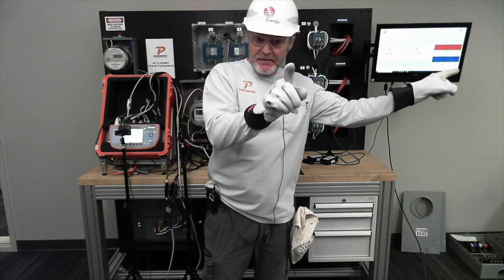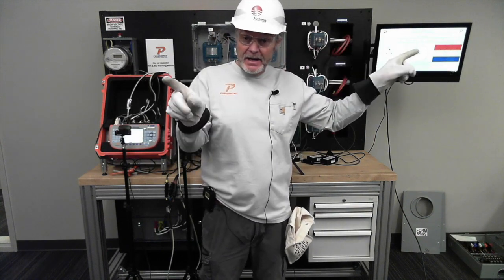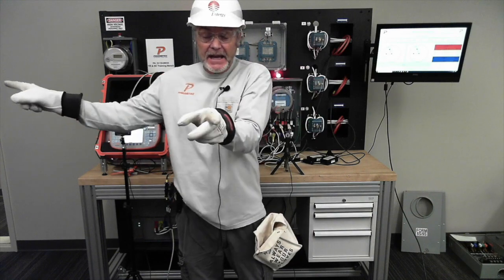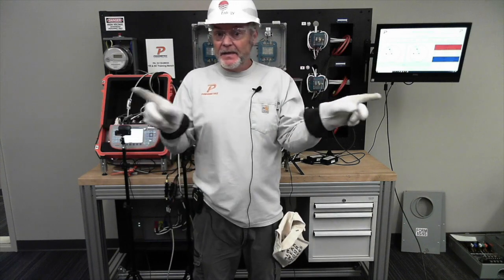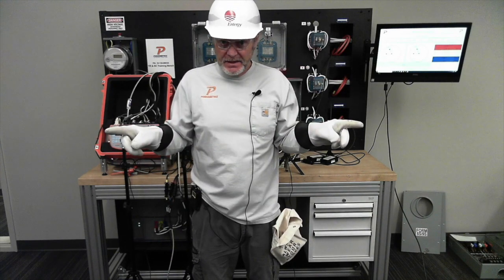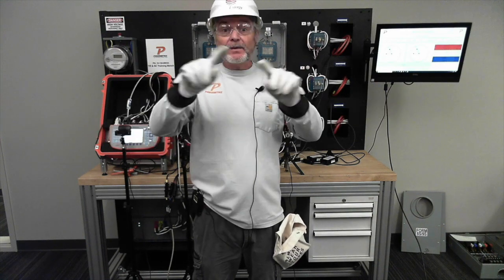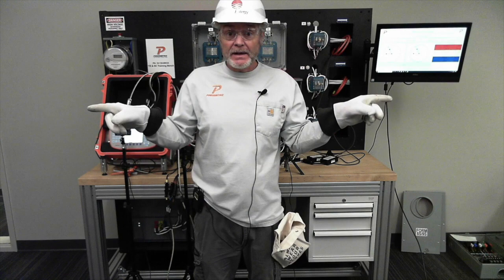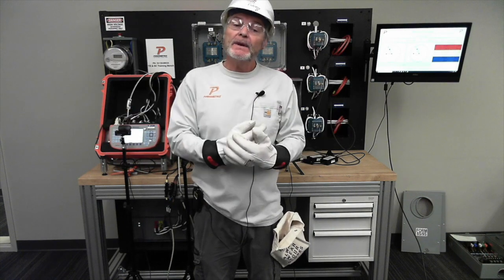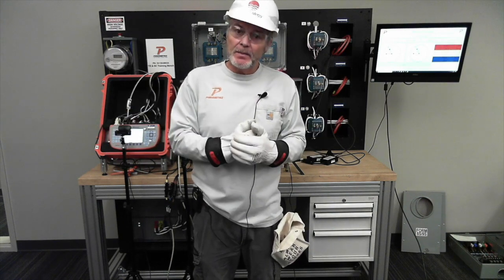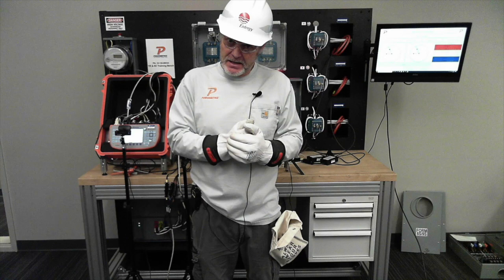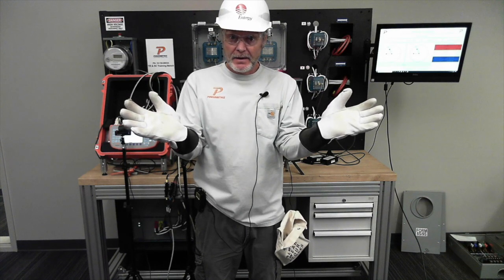Well, if my A phase primary is followed by my A phase secondary and they follow with one another, they don't see a problem between those two. So between those two, there isn't polarity reversal. Both of them are 180 degrees out, so both are falling in line with one another. So I don't get the phase angle error, I don't get the big polarity reversal messages on the screen, because it's one following the other. So as far as the two of those are concerned, they're both in line with one another.